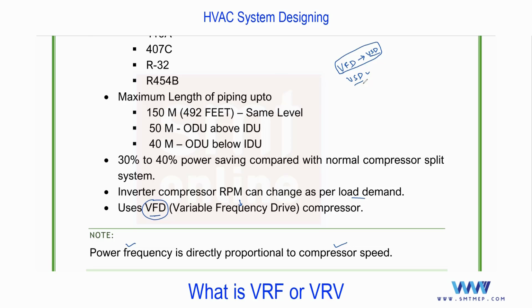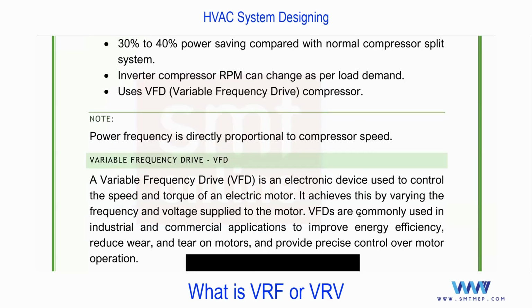So remember, VFD means by default it's a VSD, and as the speed changes, the power consumption also changes. It may increase or decrease. But if the system is only VSD, the speed can vary but the power consumption will not vary. There will be no saving in energy. Take the example of a ceiling fan. I can run a ceiling fan at speed 1, 2, 3, 4, 5, but we don't have a VFD drive connected. So the ceiling fan is a VSD, a variable speed drive, but not a variable frequency drive. The power consumption at all speeds is going to be the same. So remember, if the power frequency changes, the speed of that compressor also changes.